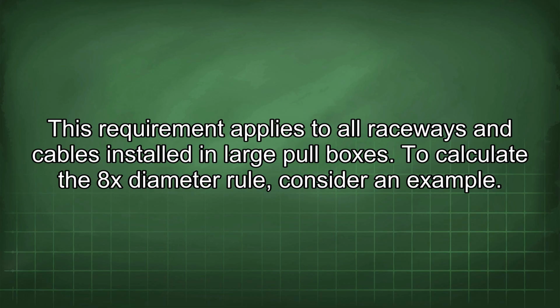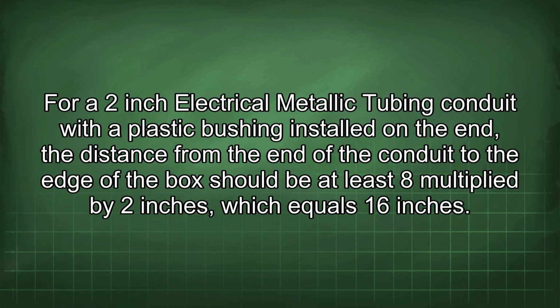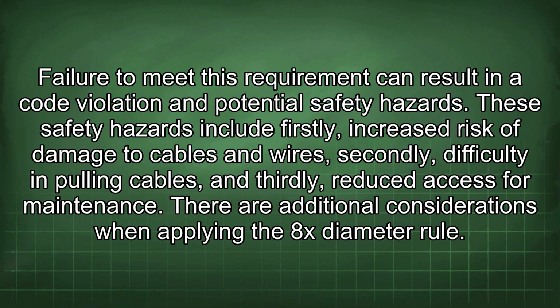To calculate the 8x diameter rule, consider an example. For a 2-inch electrical metallic tubing conduit with a plastic bushing installed on the end, the distance from the end of the conduit to the edge of the box should be at least 8 multiplied by 2 inches, which equals 16 inches. Failure to meet this requirement can result in a code violation and potential safety hazards.